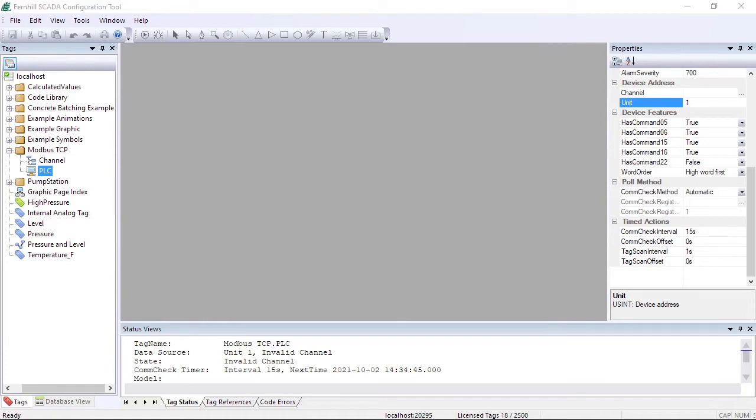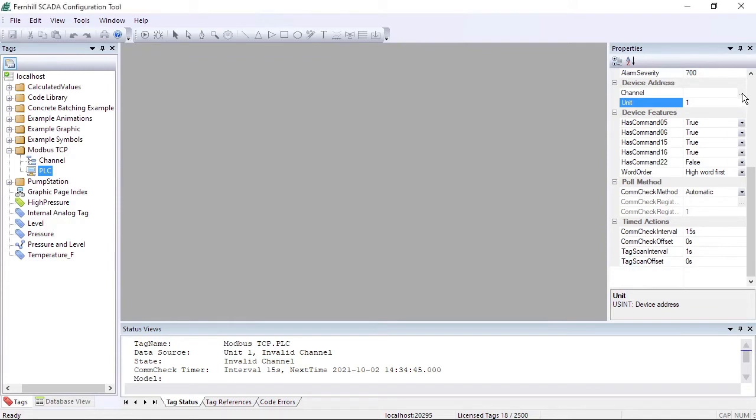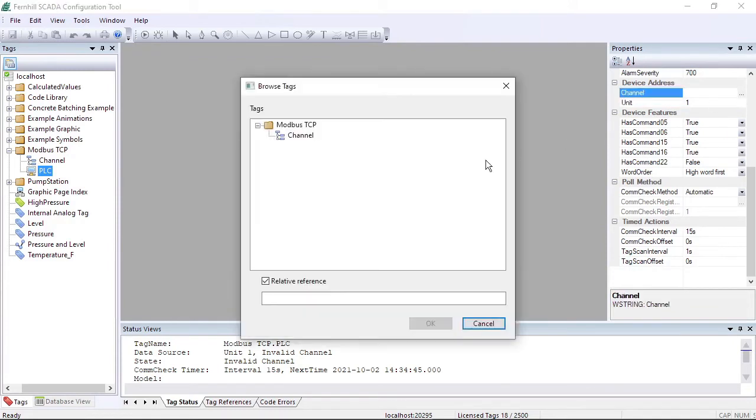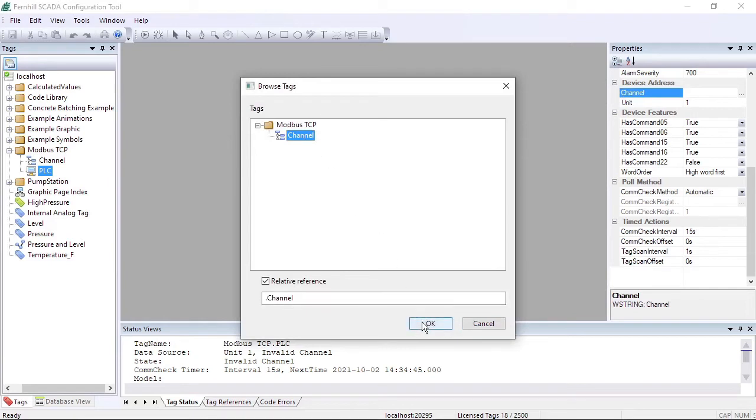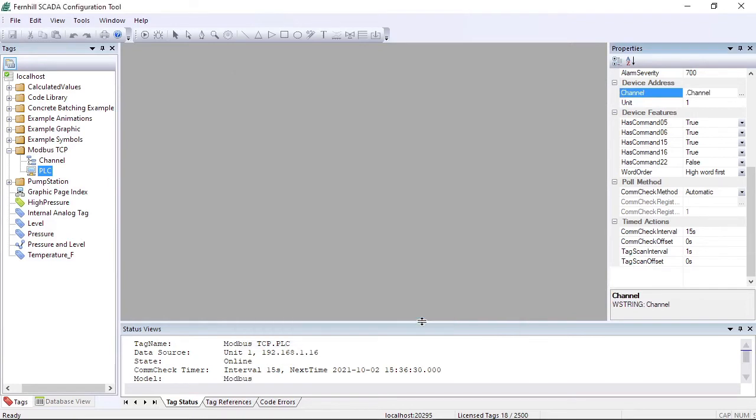The final part of the setup of the PLC device tag is to set the channel property. To do this, click the browse button next to the channel property of the PLC device tag, select the channel we created in an earlier step, and click OK. We can check the tag status window to confirm the PLC is now online.